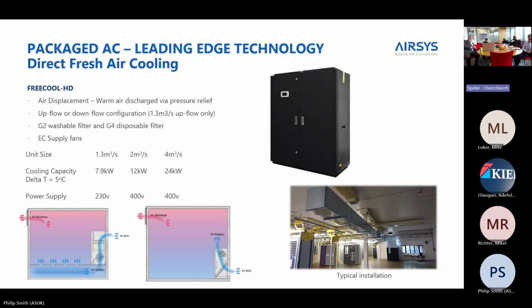And then finally, we have just fresh air, which, you know, in this country, fresh air will give you free cooling and cooling for a large percentage of the year. Again, it is not guaranteed. Now, for example, BT will put one of these units in, typically a 2 meter cube a second unit. But what it means is that in winter, it brings fresh air. But in winter, it can nigh on replace the use of a CRAC unit. So it almost becomes a priority cooling. It then backs off the refrigerant in any other unit and then saves them the money. During the summer, obviously, it is then just bringing fresh air in for occupancy. So it'll work on a two-fold basis.